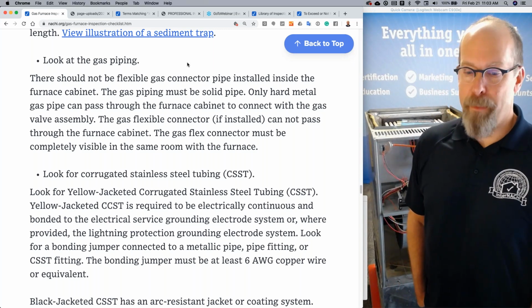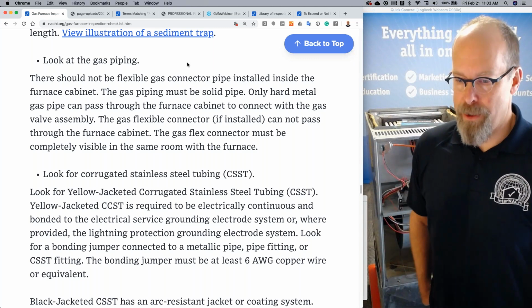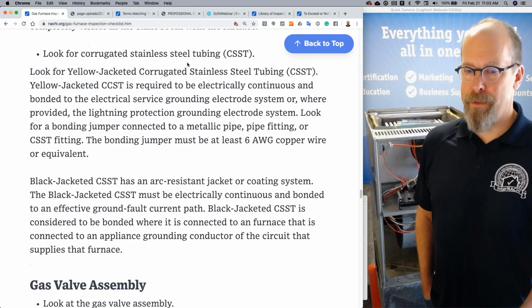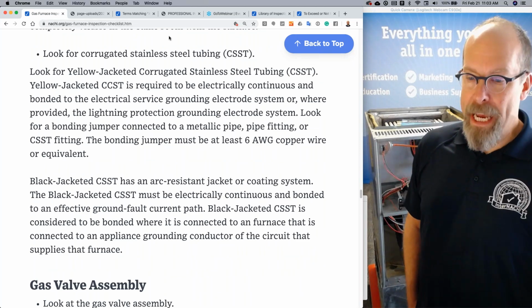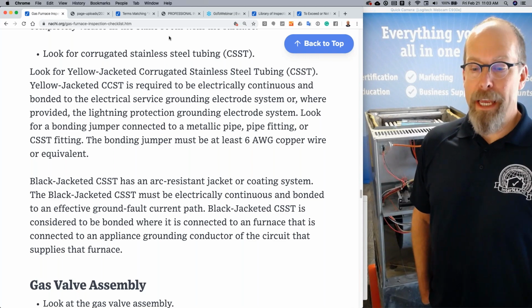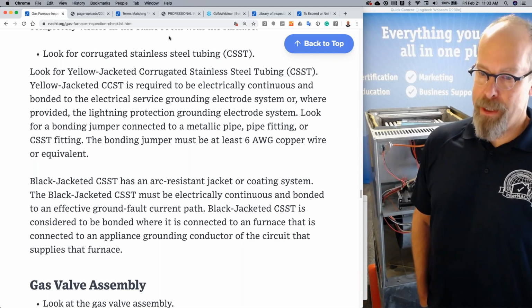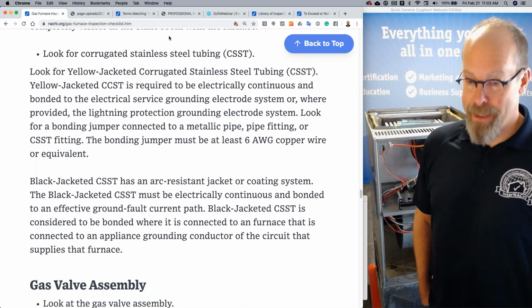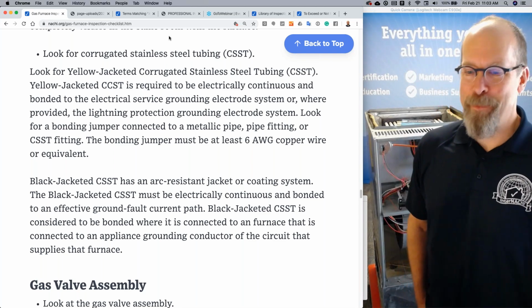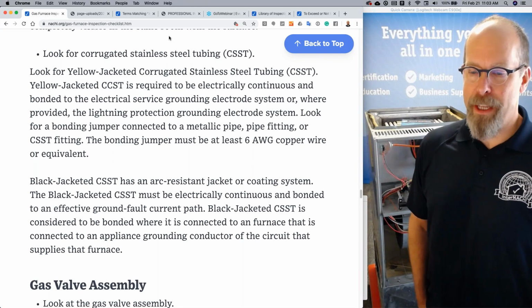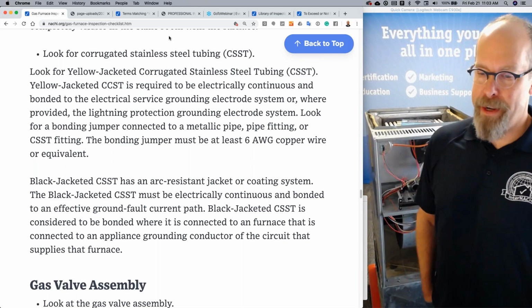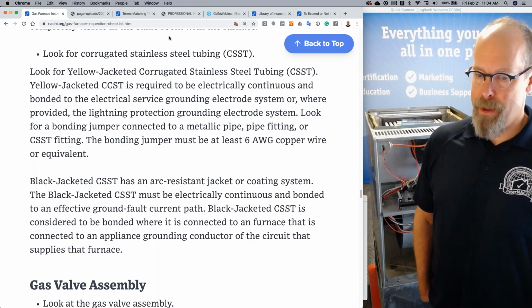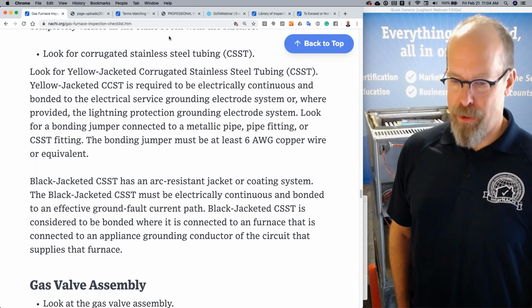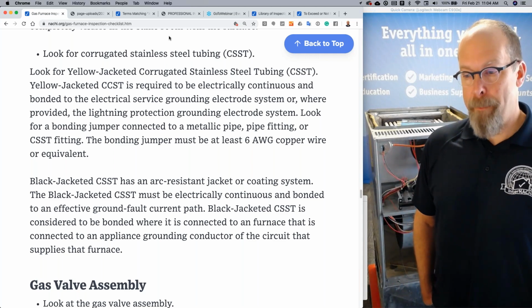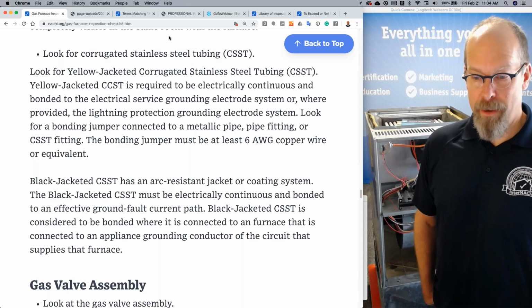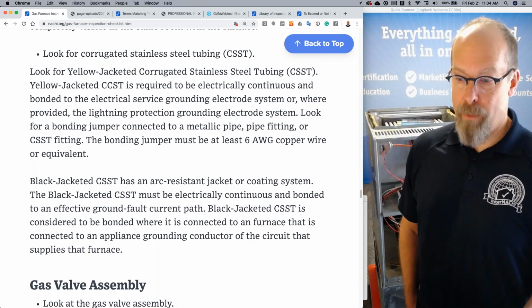The gas flex connector must be completely visible in the same room with the furnace, the whole section. Look for CSST, the corrugated stainless steel tubing. Look for yellow jacketed or black jacketed. Yellow jacketed CSST is required to be electrically continuous and bonded to the electrical service grounding electrode system, or, where provided, the lightning protection grounding electrode system. So look for a bonding jumper when you have the yellow jacketed. That's connected to a metal pipe fitting, or the CSST fitting. The bonding jumper is 6 gauge or equivalent.